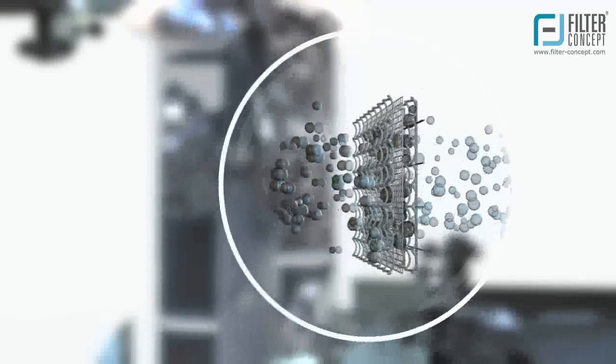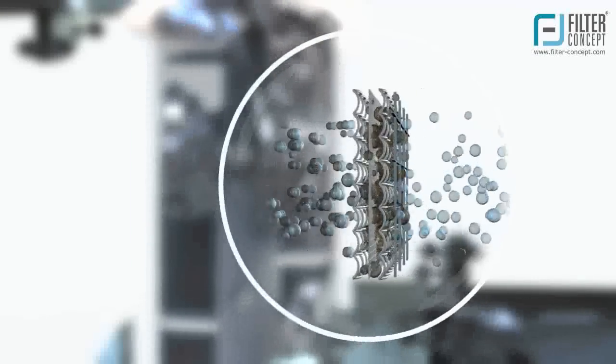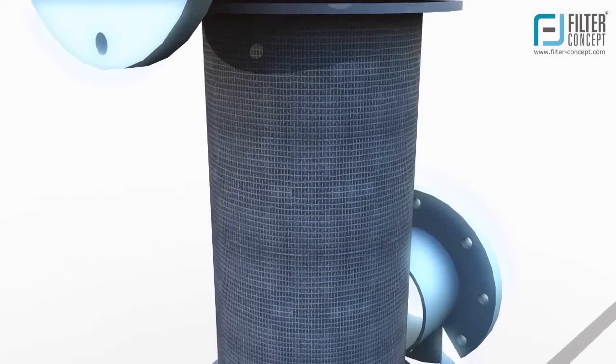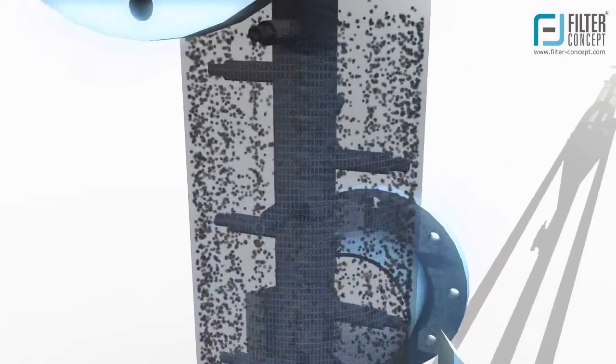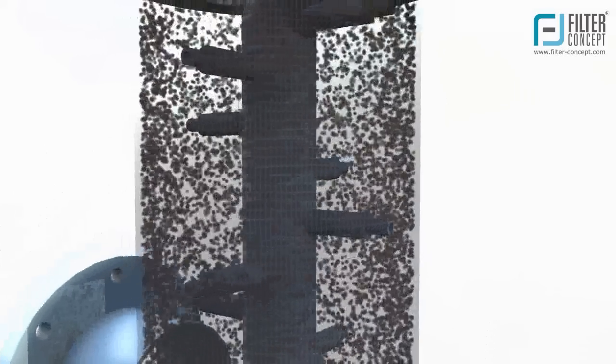Suspended particles of defined micron rating are retained inside. Suspended particles retained inside filter element create a layer of debris, resulting in increased differential pressure.